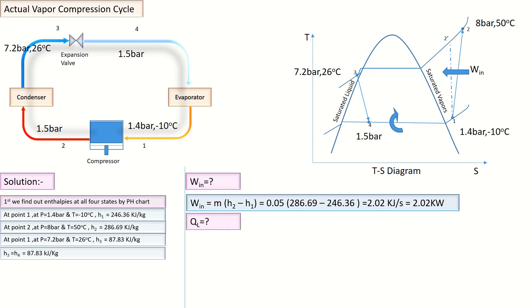Now, how much heat is absorbed in evaporator from the refrigerated space to provide the cooling effect? It is calculated by the difference of enthalpies multiplied by the mass flow rate. Enthalpy at Point 1 is 246 kJ/kg and Point 4 is 87 kJ/kg. By calculating, we find Q_e = 7.93 kilowatts of heat will be absorbed in evaporator.